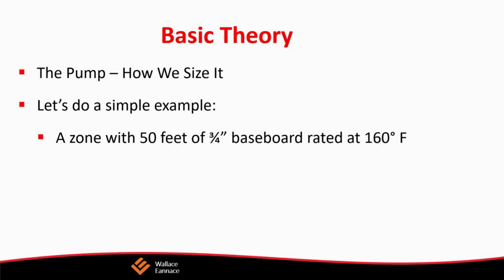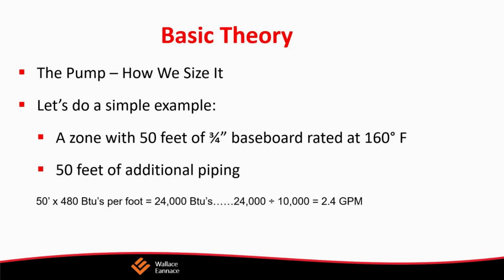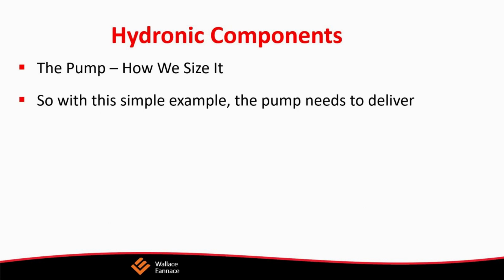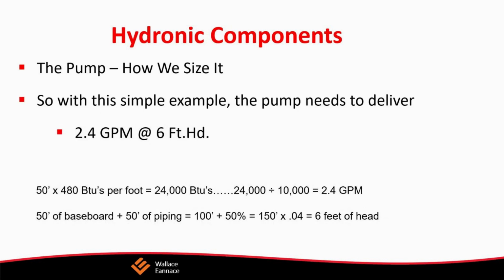So when sizing a pump, the first thing we have to realize is that system flow is kind of like a Ferris wheel. The weight of the water going up equals the weight of the water going down. So really, in a closed system like a hydronic system, the actual height of the building has no effect on the sizing of the pump and the amount of head pressure that you need for the pump. Really, in this particular case, like the Ferris wheel, it only has to overcome the friction of the system. So when calculating pump head, we don't really care what the height is.